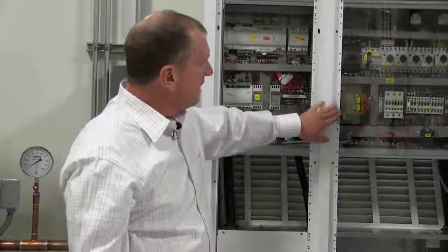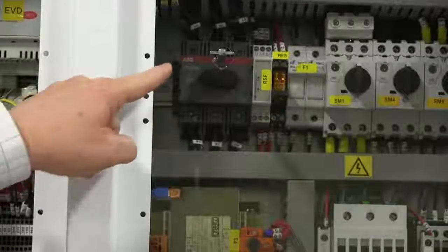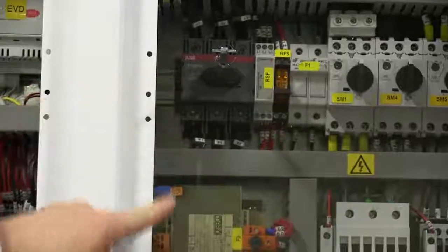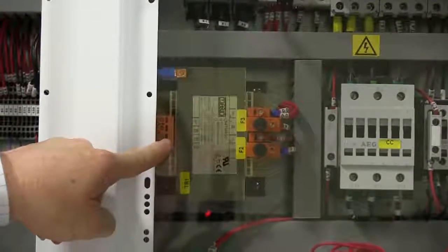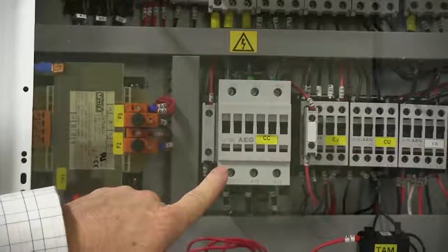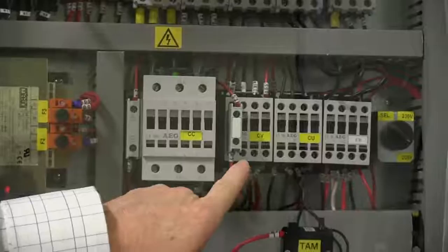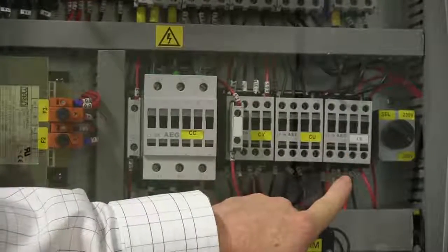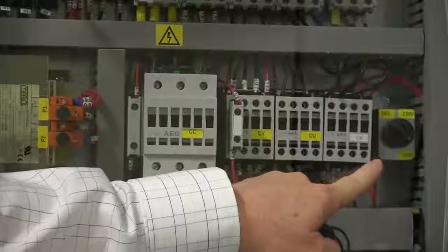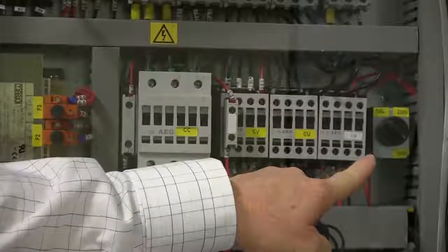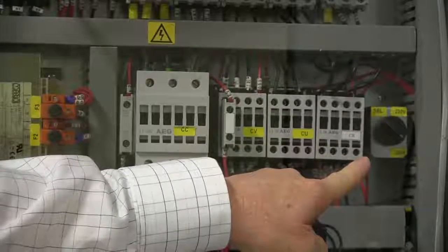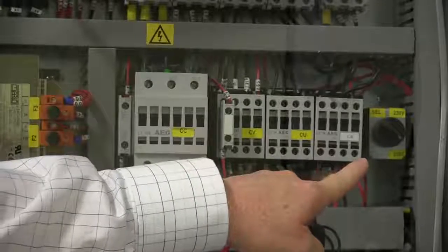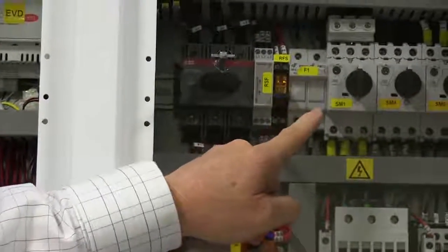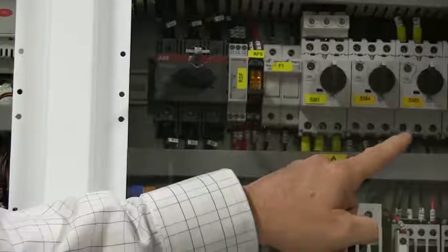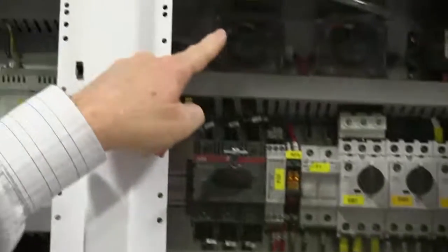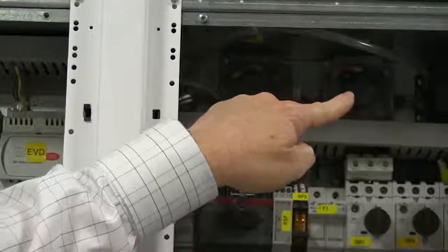Now we'll move to the high voltage side of the electrical panel and talk about some of the components. We have our non-fuse disconnect switch. We have our control transformer for the control circuit. We have contactors for the compressor, for the fan, for the humidifier, and for the electric reheat. And finally, in line here, we have the selector switch for control voltage. This is a 208/230 volt unit, and to allow precise control on the control circuit voltage, we actually select the exact incoming voltage. Then we have our overload relays for the compressor, fan, humidifier, and electric reheat. And finally, at the top, we have our fan pressure switch and our dirty filter pressure switch.